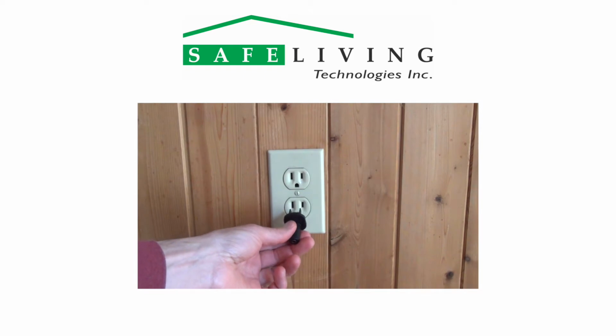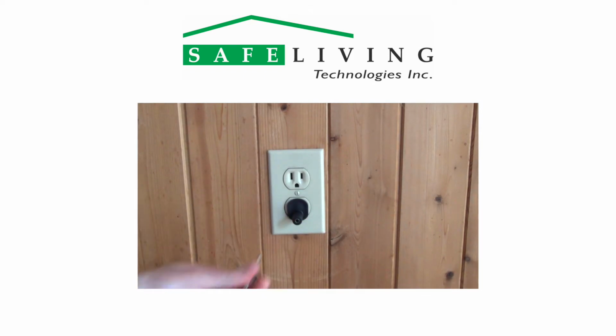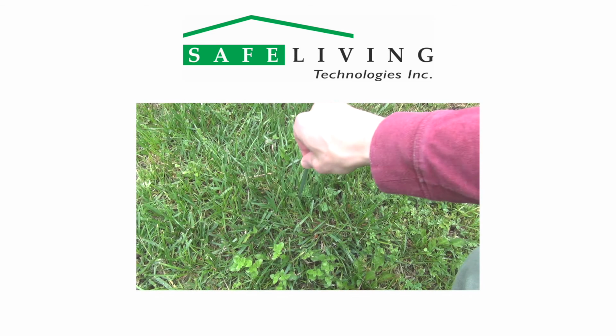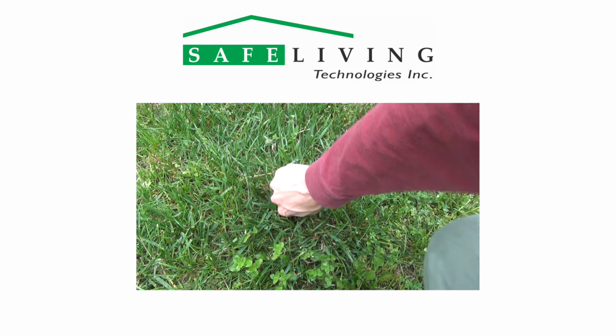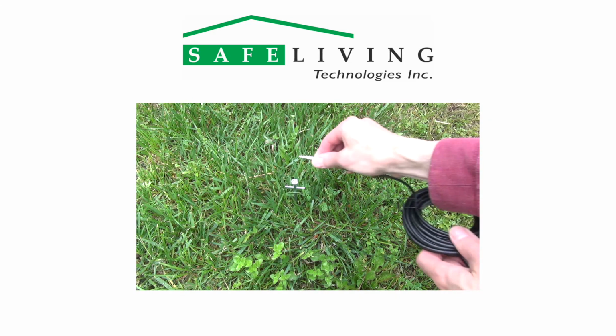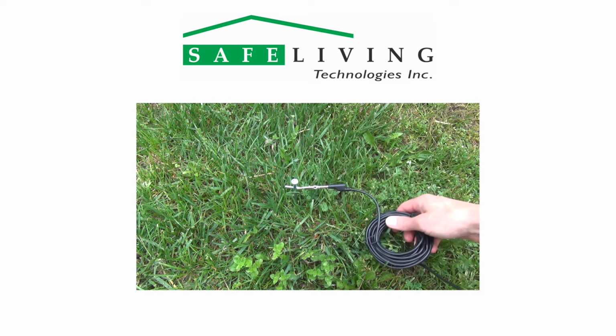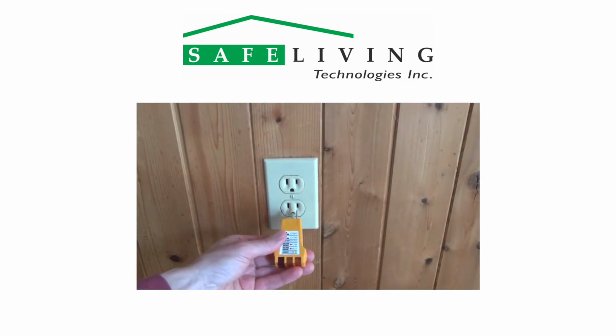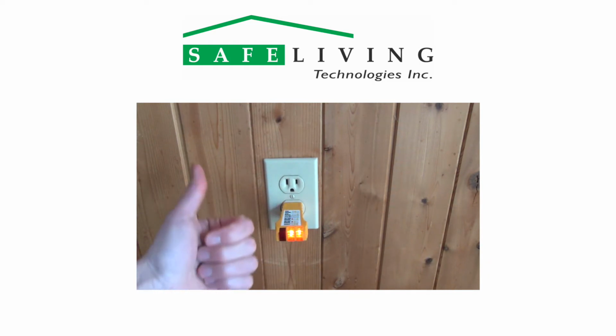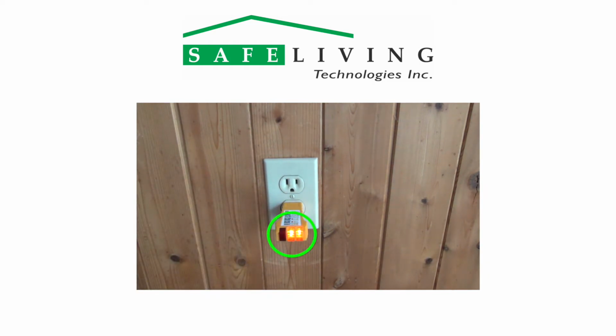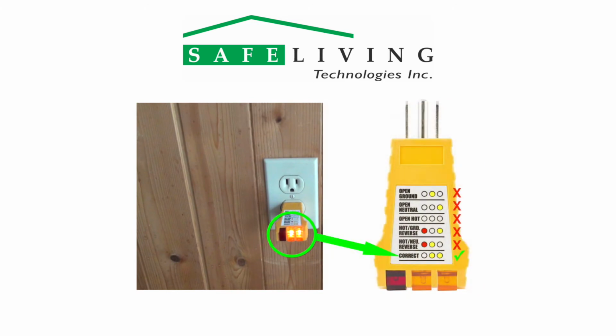To measure, you will need to connect the meter to a known ground point. This can be with the included grounding plug as shown, or by using the included grounding rod inserted to the earth outside as shown. Before using a grounding plug, it is very important to test the AC outlet for correct wiring. Shown here is the indication for proper wiring. If the tester fails to show these two lights, do not use that outlet as a ground connection and have the wiring fixed by a licensed electrician.